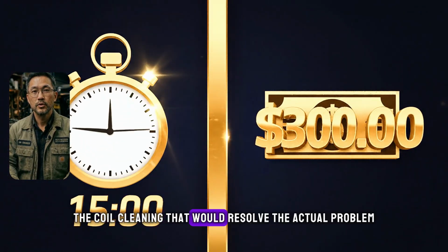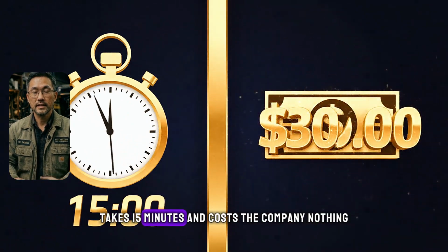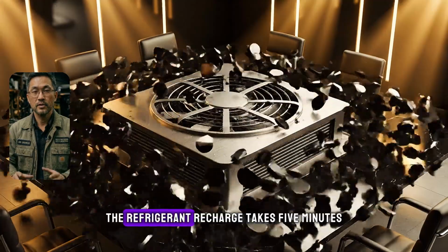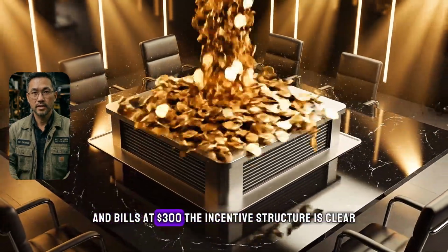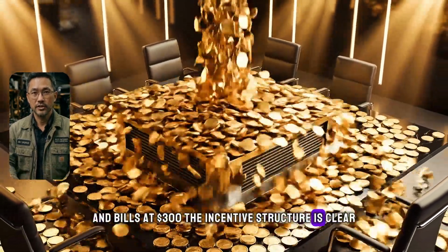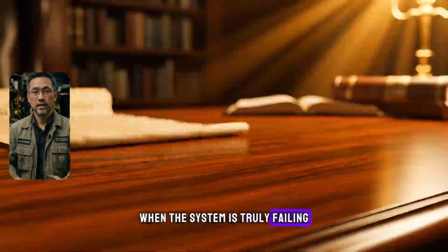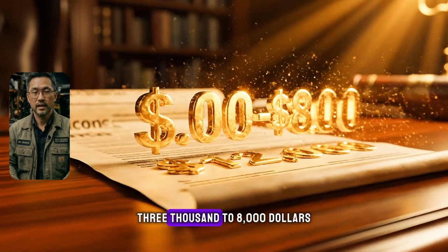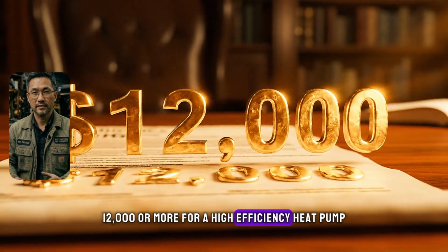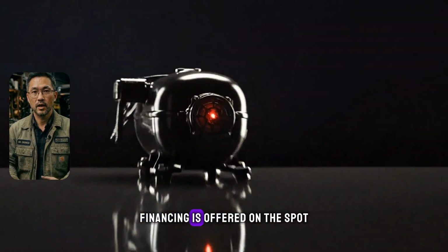The coil cleaning that would resolve the actual problem takes 15 minutes and costs the company nothing. The refrigerant recharge takes 5 minutes and bills at $300. The incentive structure is clear. When the system is truly failing, the replacement quote arrives. $3,000 to $8,000 for a residential system, $12,000 or more for a high-efficiency heat pump. Financing is offered on the spot.